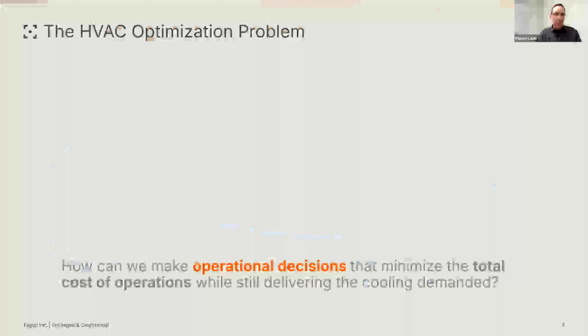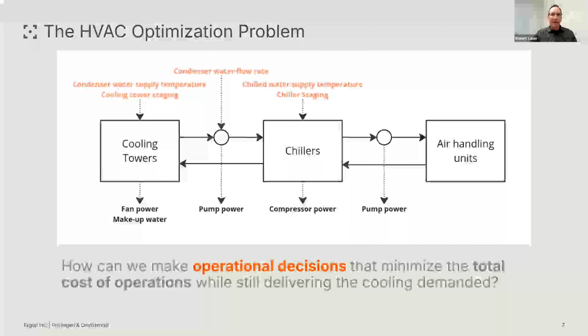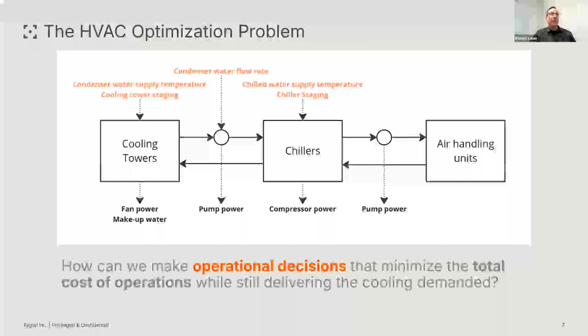The problem specifically on the cooling side that we focus on is captured here in a simplified way. Let's start on the right side, where an air handling unit comes into play. Somehow the air, through all kinds of VFDs and equipment, the heated air has made its way into the air handling unit, and the heat gets dumped into a chilled water loop. There's some kind of chiller, and in general there will be more than one, possibly different types, that removes that heat and moves it into a different circuit.